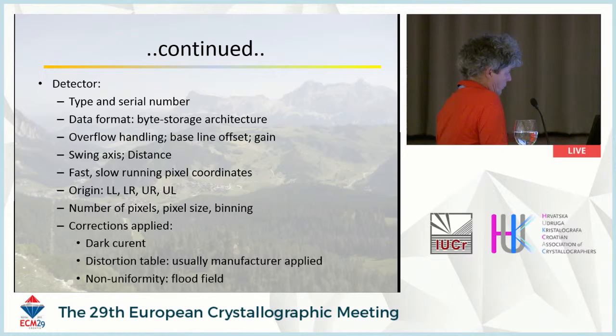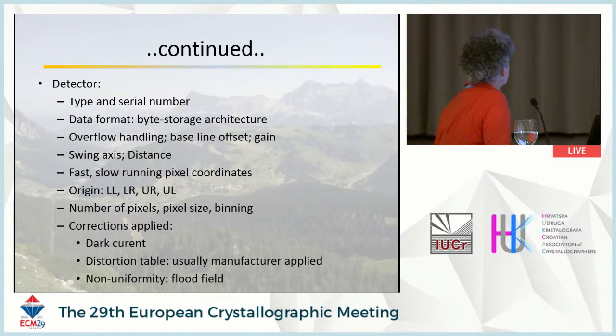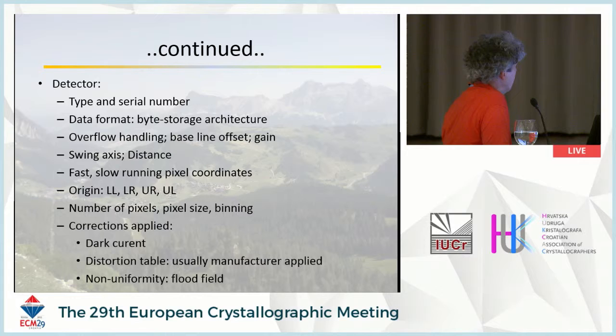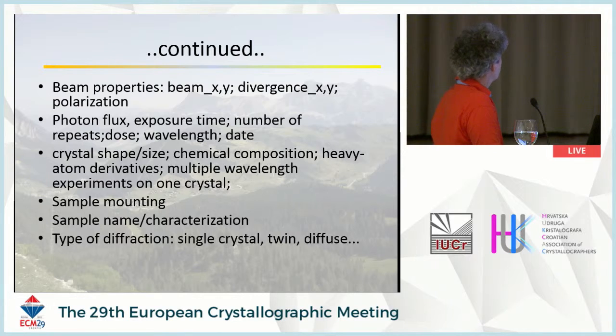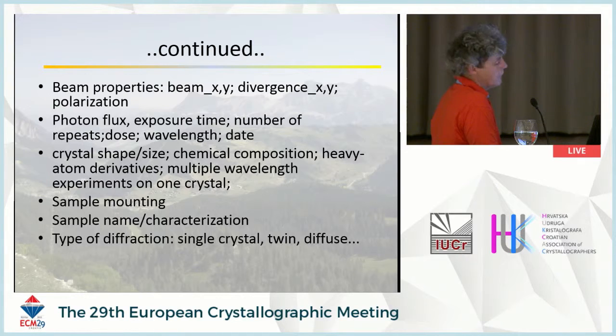We also need to know which corrections have already been applied to the raw images, because raw images are often not truly raw — dark current may have been subtracted, distortion correction may already have been applied by the manufacturer, and non-uniformity corrections may be applied. For beam properties, we need the position of the primary beam, divergence in two directions, polarization, photon flux, exposure time, number of repeats, dose, wavelength, and date.